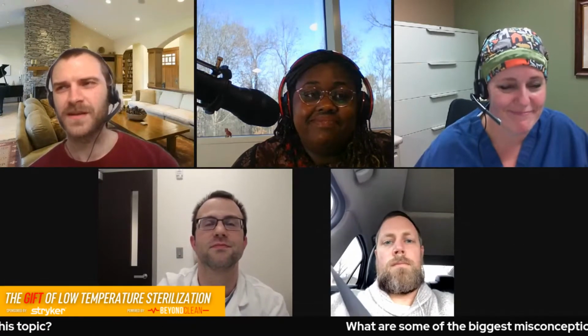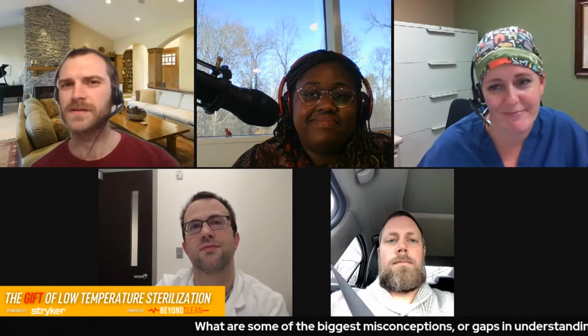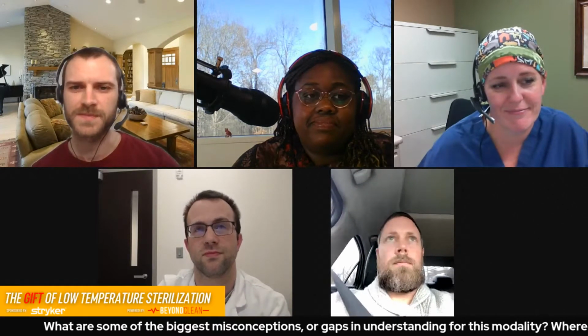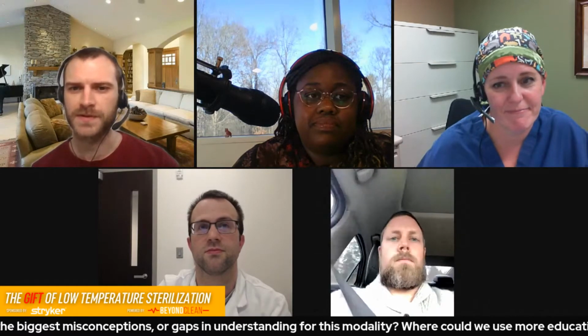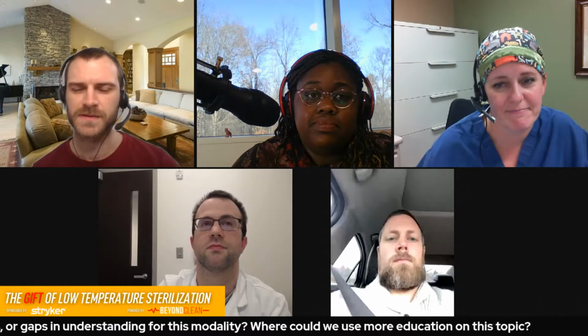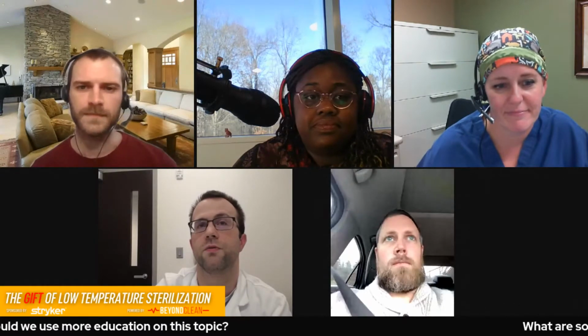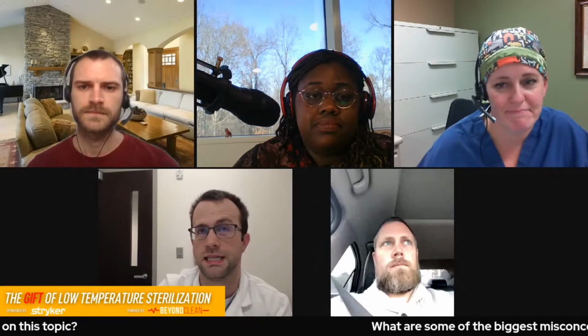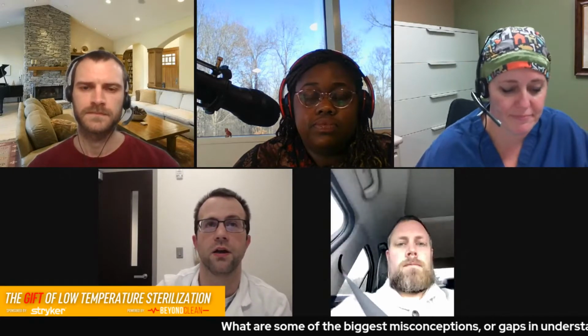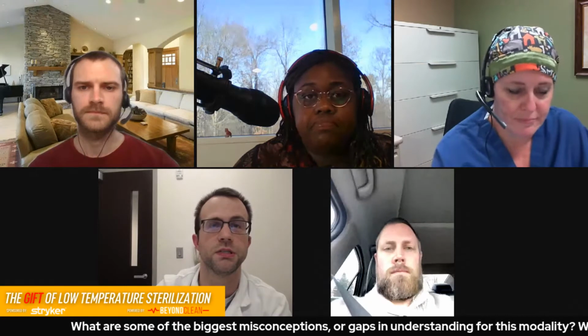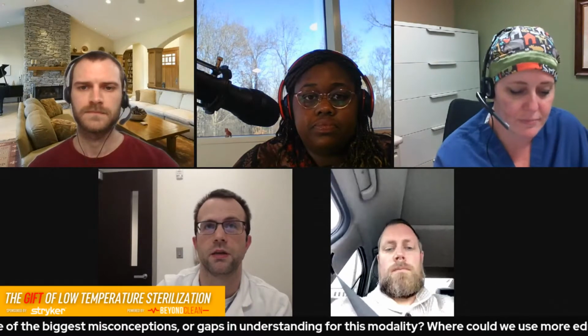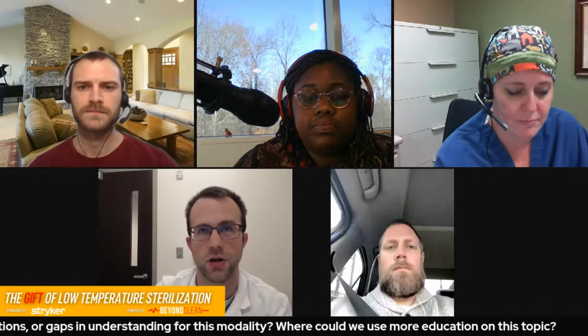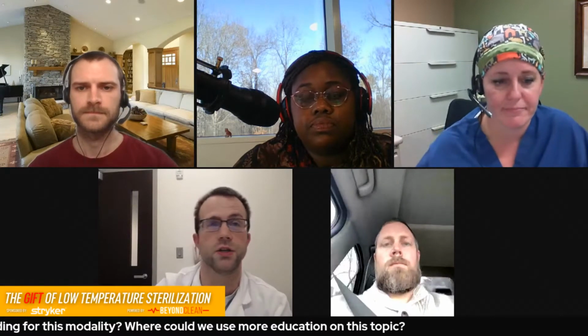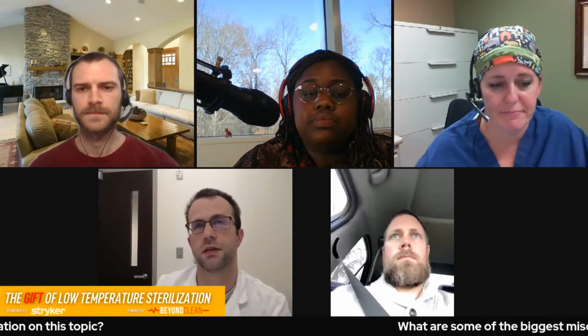Yeah. So Jake, help our hearers out with this issue. So you have an IFU in front of you that's brand specific. Is your only option to go purchase a different device or a different sterilizer, or is there some work that a hospital or a facility can do to stay compliant? So I would reach out first to the instrument manufacturer because they may have an updated or a letter of addendum to those IFUs. And then I would also reach out to the sterilizer manufacturer because they may have some other documents. And if they contradict, I would always go right back to the instrument manufacturer to make sure there's nothing that's been forgotten or missed.